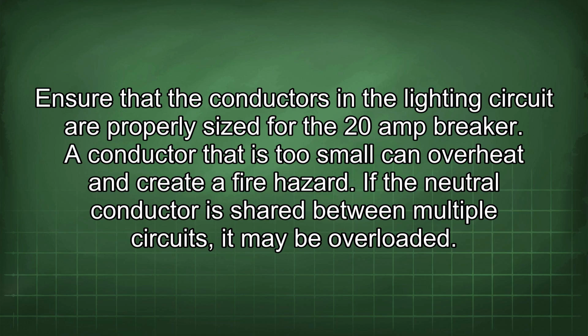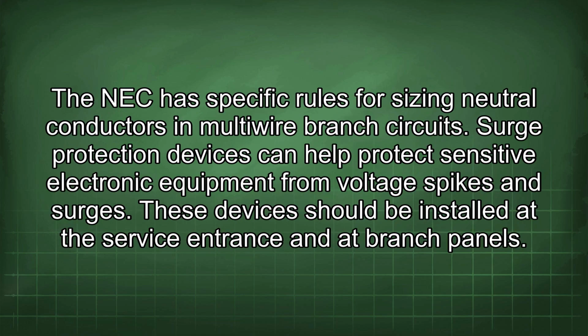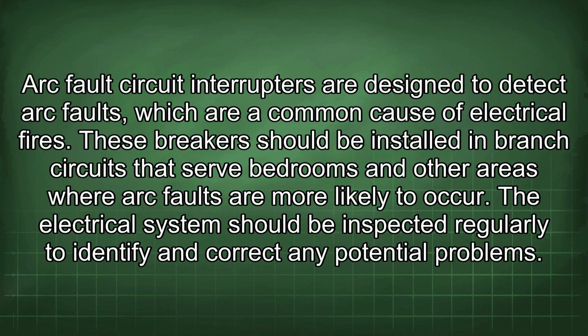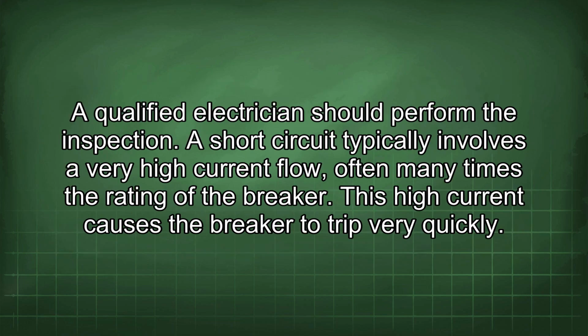If the neutral conductor is shared between multiple circuits, it may be overloaded. The NEC has specific rules for sizing neutral conductors in multi-wire branch circuits. Surge protection devices can help protect sensitive electronic equipment from voltage spikes and surges. These devices should be installed at the service entrance and at branch panels. Arc fault circuit interrupters are designed to detect arc faults, which are a common cause of electrical fires. These breakers should be installed in branch circuits that serve bedrooms and other areas where arc faults are more likely to occur. The electrical system should be inspected regularly to identify and correct any potential problems. A qualified electrician should perform the inspection.